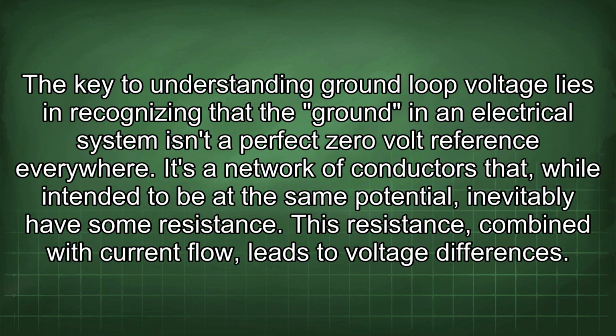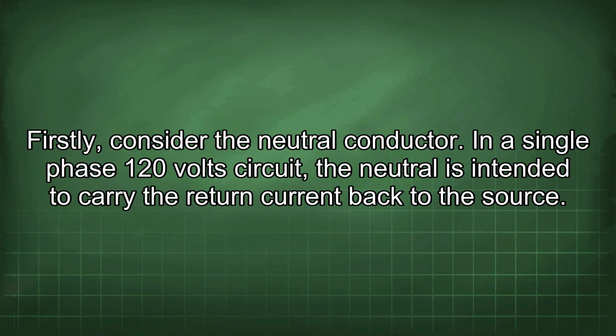The key to understanding ground loop voltage lies in recognizing that the ground in an electrical system isn't a perfect 0-volt reference everywhere. It's a network of conductors that, while intended to be at the same potential, inevitably have some resistance. This resistance, combined with current flow, leads to voltage differences. Firstly, consider the neutral conductor.